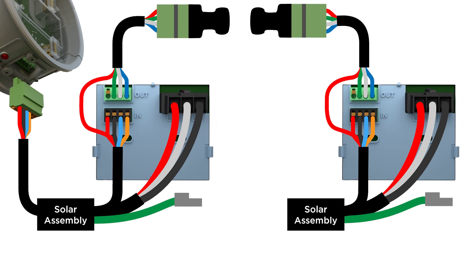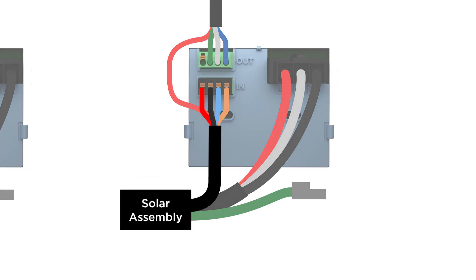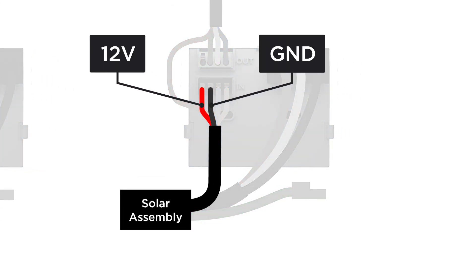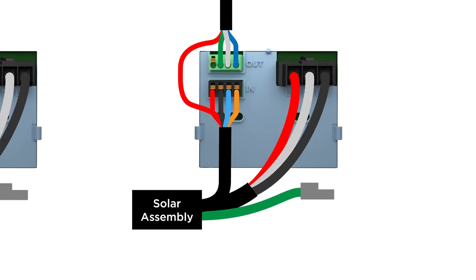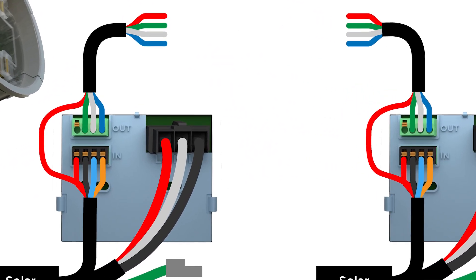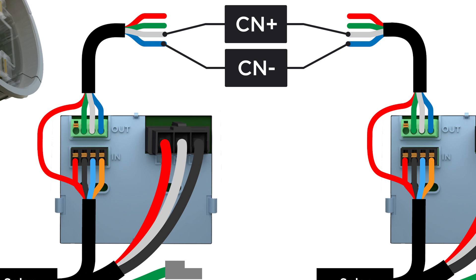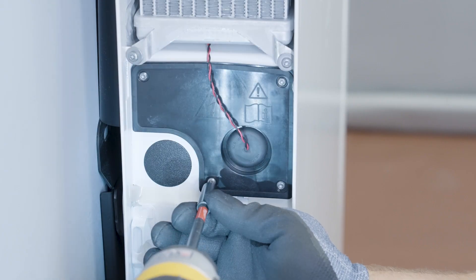Since the battery assembly of an Expansion Powerwall Plus already has 12-volt and ground from the inter-product harness, only the CAN high and CAN low are required to be connected between the two units. Open the wiring compartment of both Powerwall Pluses.